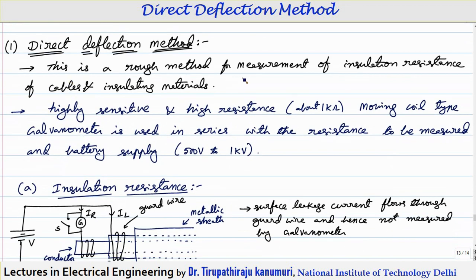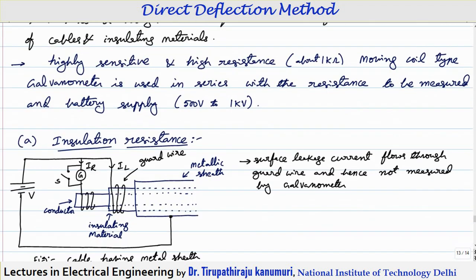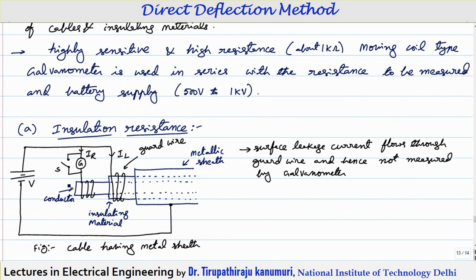This is a rough method used for measurement of insulation resistance of cables as well as insulating materials. Because the value of the resistance is very high, for a given voltage — let's assume applying about 500 volts and resistance equal to 1 mega ohm — voltage divided by resistance means the current will be very less. In order to sense that small value of current, whichever galvanometer you are using should have very high sensitivity.